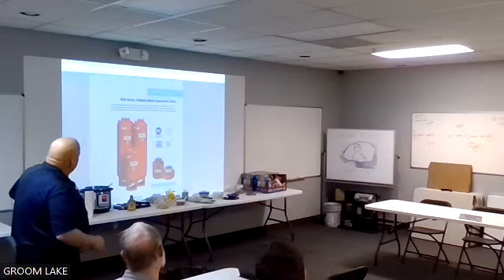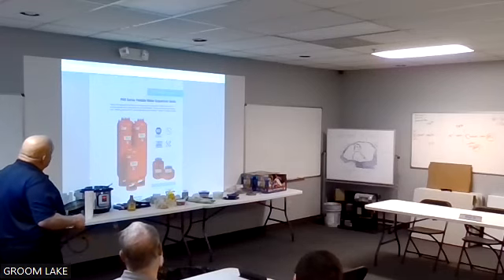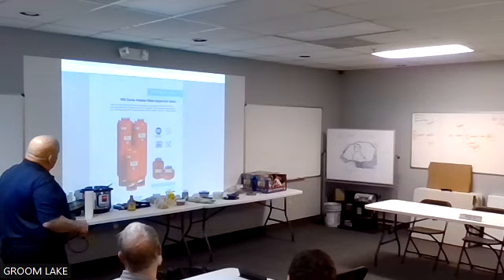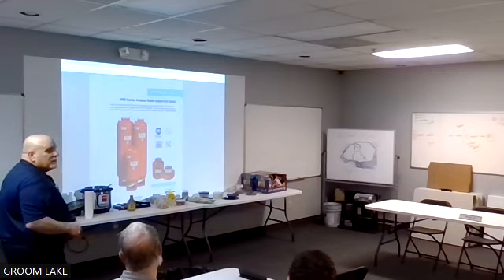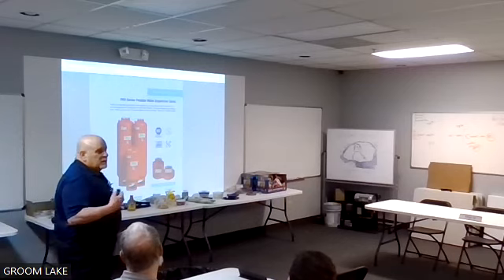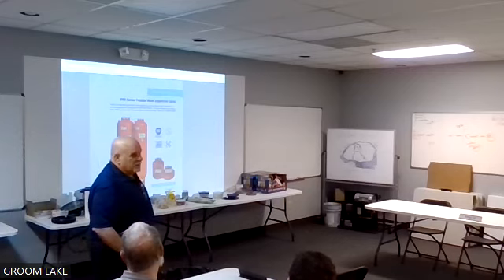And the only other difference is it has the same bladder in it, 150 PSI, but if you note on the top of these, this whole head is stainless. And this is stainless because these are for domestic hot water. Domestic hot water is horribly corrosive.